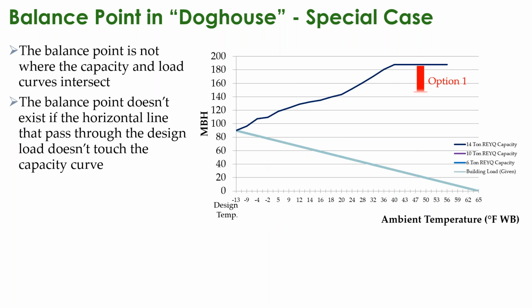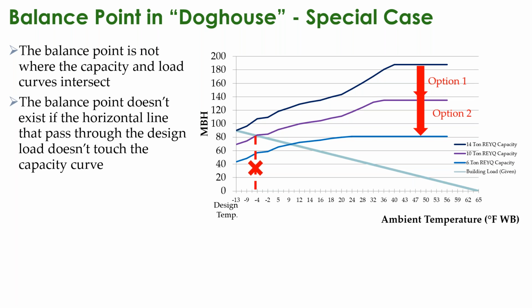Just to reinforce this a little bit more, again, your 14-ton, you're covering your entire load, but you have to consider the cost and the ramifications of operation of that system in the long term. You've got your 10-ton that your intersect is minus 4 degrees, but that is not your balance point.